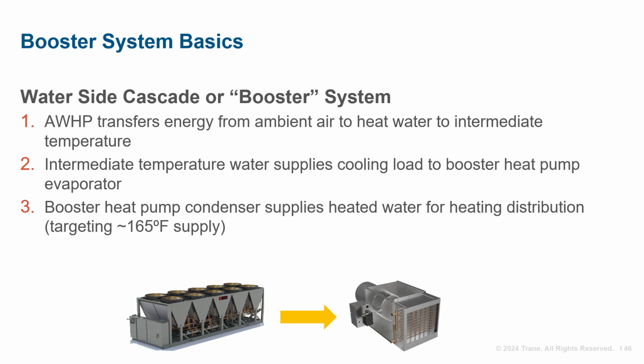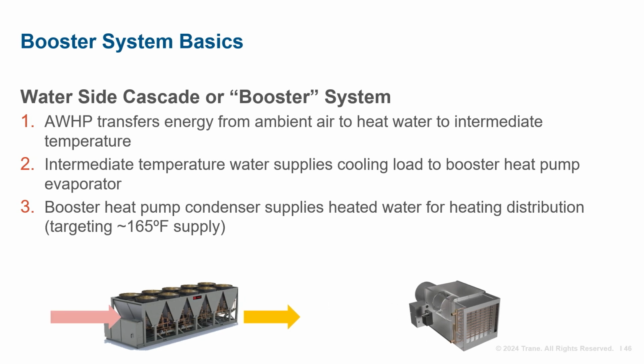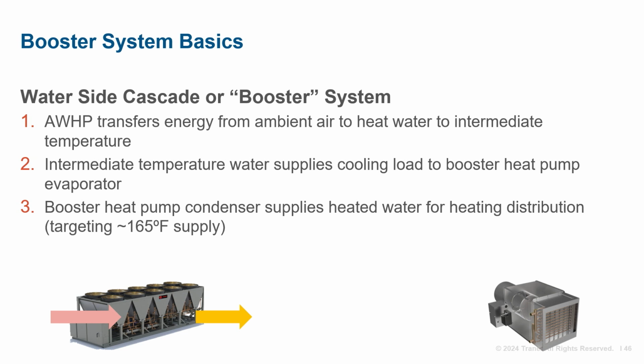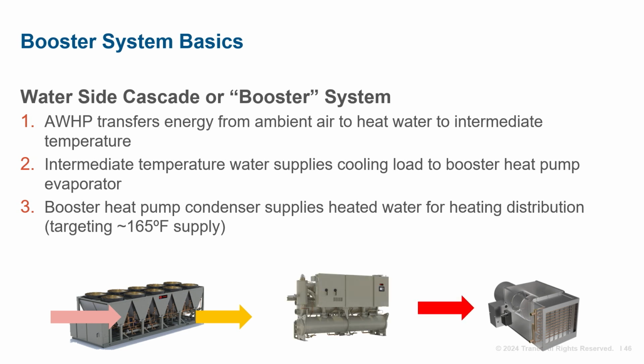Cascade or booster systems add a second unit to boost the hot water supply temperature to temperatures not attainable with only one unit. In this case, an air-to-water heat pump operating and heating at cold ambient conditions may only be able to provide 90 to 100 degrees Fahrenheit hot water supply temperature. Instead of sending that warm hot water to the building terminal units, it's sent to a booster heat pump evaporator, creating an intermediate loop. The booster condenser can then be piped to the building terminals and supply hot water temperatures of 160 or even as high as 200 degrees, depending on the unit.